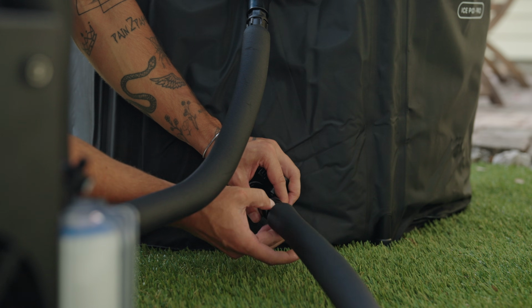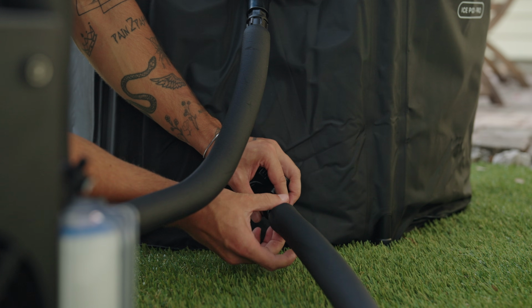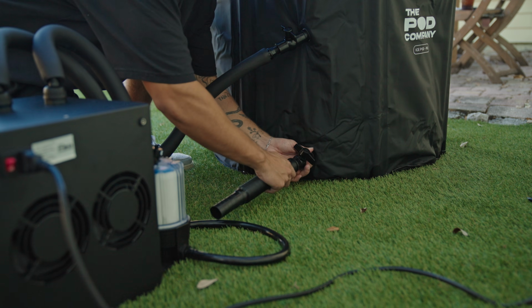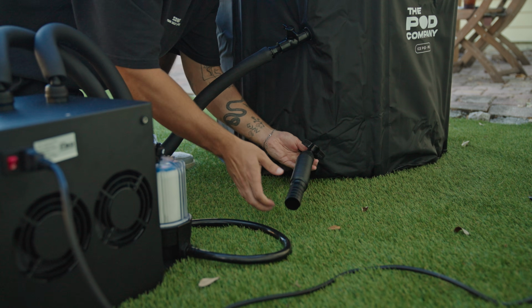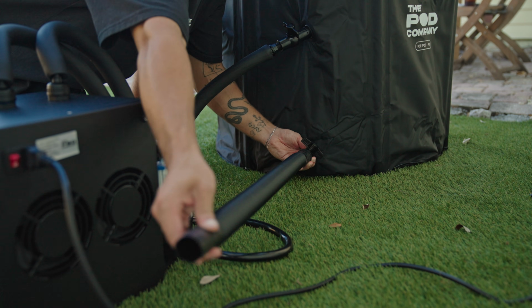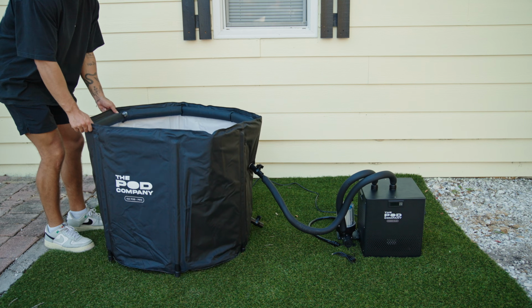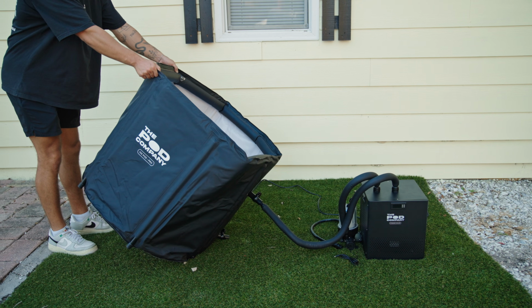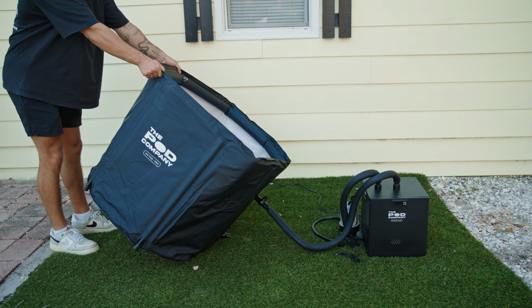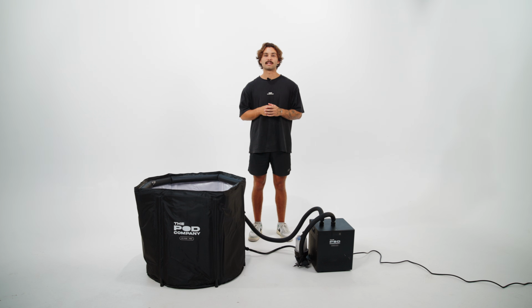Close both valves and disconnect the hose from the lowest drain valve. Attach the included 3-foot drain hose or the extended 9-foot hose to drain the water. Gently lift the IcePod from the opposite side of the valves to let the remaining water drain out. After draining, follow the same steps to remove the filter as we showed earlier. Dispose of the old filter and install the new one. Once the new filter is in place, hand tighten the housing and follow the setup steps to restart the chiller and ensure it's circulating properly.